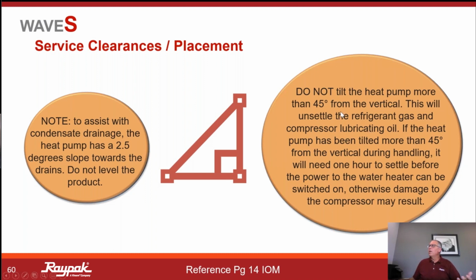Do not tilt the heat pump more than 45 degrees from vertical. I think this is true when you're moving a refrigerator. You don't want that refrigerant to get a particular way. So if you do, it needs to sit for a period of time to settle. So this is in keeping with what you might have already seen with other refrigerant-based equipment.